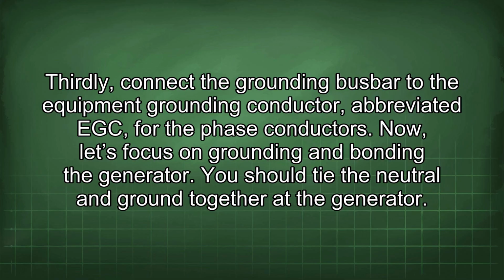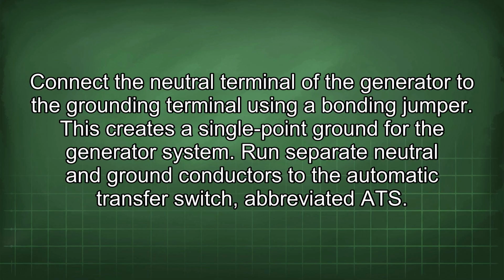Now let's focus on grounding and bonding the generator. You should tie the neutral and ground together at the generator. Connect the neutral terminal of the generator to the grounding terminal using a bonding jumper. This creates a single point ground for the generator system.